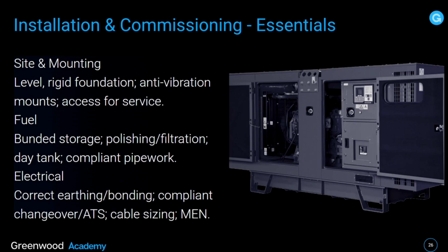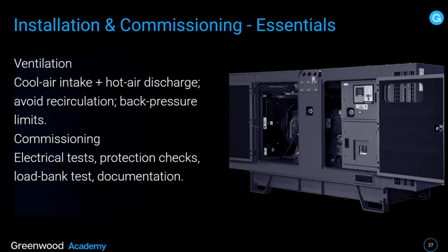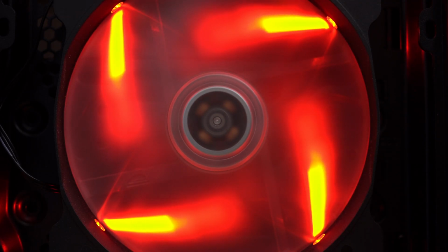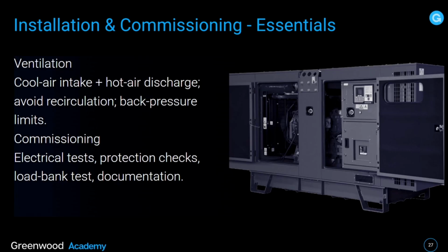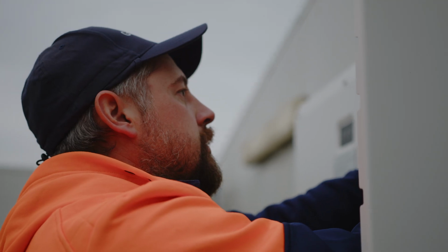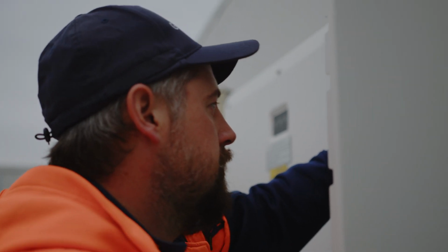Fuel is really important. We're talking about potentially bunded storage, polishing, filtration, day tank, and all the compliant pipework. And of course, there's the electrical: correct earthing, bonding, compliant changeover, ATS, automatic transfer switch, cable sizing, and the multiple earth neutral. And of course, there's ventilation, cool air intake and hot air discharge, and you must avoid recirculation and back pressure limits. Of course, there's a commissioning component, and you must take into consideration the electrical tests, the protection checks, load bank test, and the documentation.